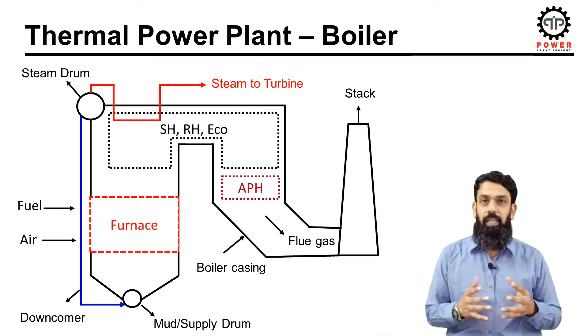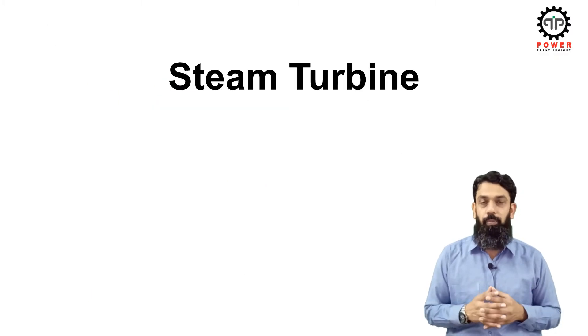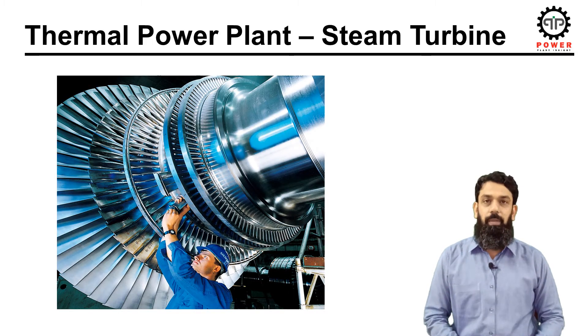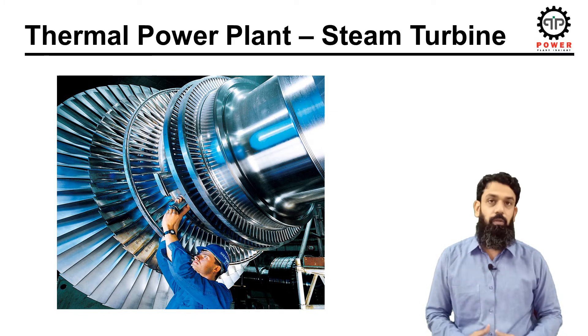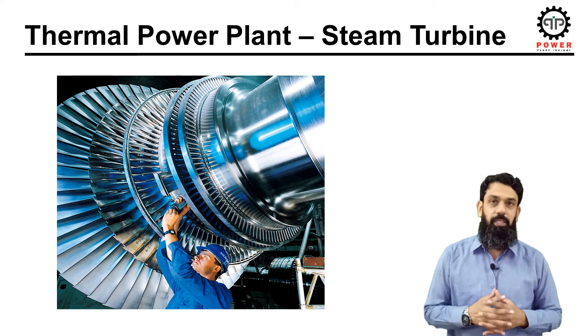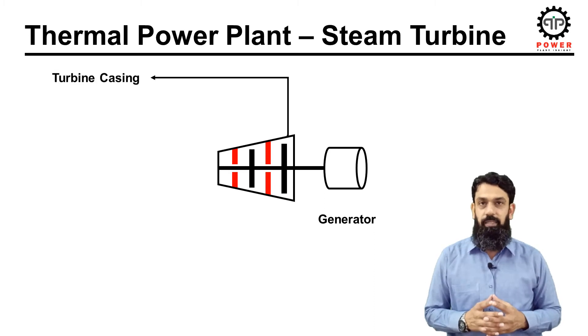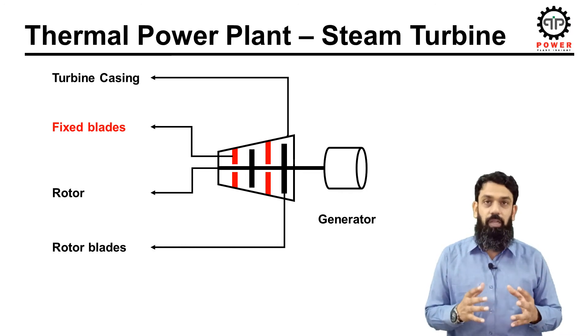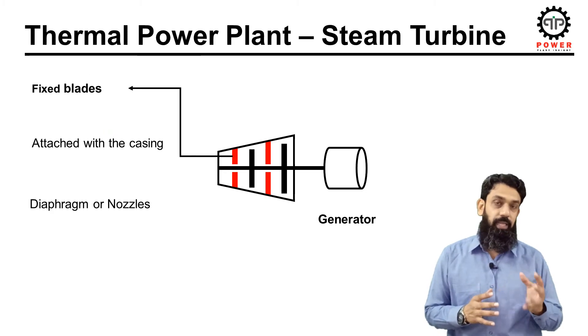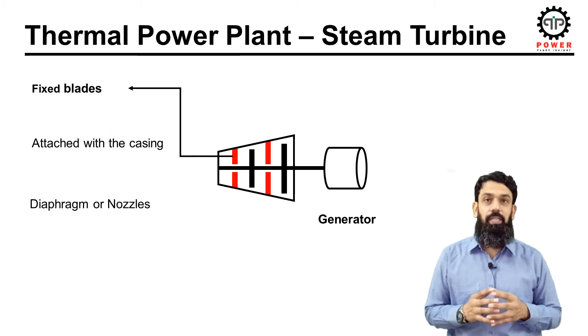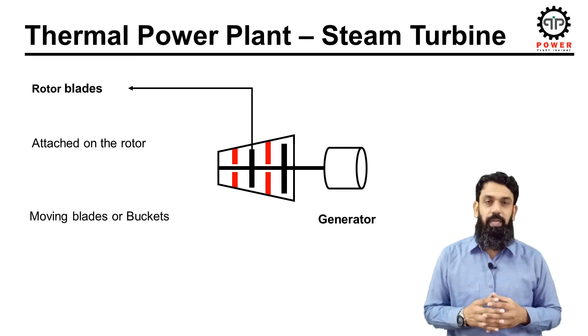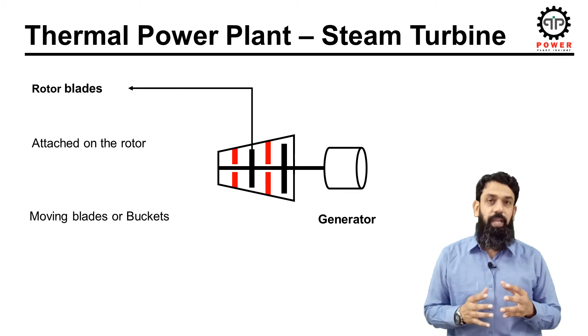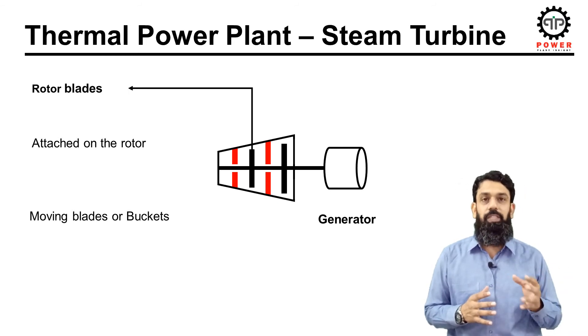Now let's move to our next main component: the steam turbine. Steam turbines are used to convert the thermal energy of steam into mechanical energy. Generally speaking, a steam turbine consists of turbine casing, fixed blades, rotor, and rotor blades. The turbine casing forms the outer covering of the turbine. Fixed blades are attached to the turbine casing and are also called nozzles or diaphragms. Rotor blades are also called buckets or moving blades. The rotor consists of a shaft with rotating blades; the rotor shaft extends beyond the turbine casing through a bearing case, which is coupled with the generator to generate electricity.